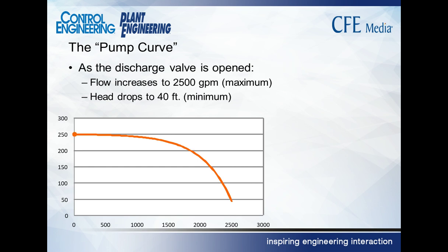So open the valve back up, and the flow will increase. So I'm using a flow control valve, a discharge, or a throttle valve to control the flow through the pump. And if I open it all the way up, it goes up to about 2,500 gallons per minute for this particular pump, and I'll have about 40 feet of head.